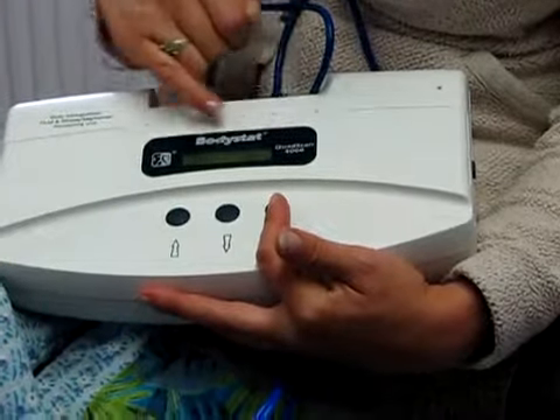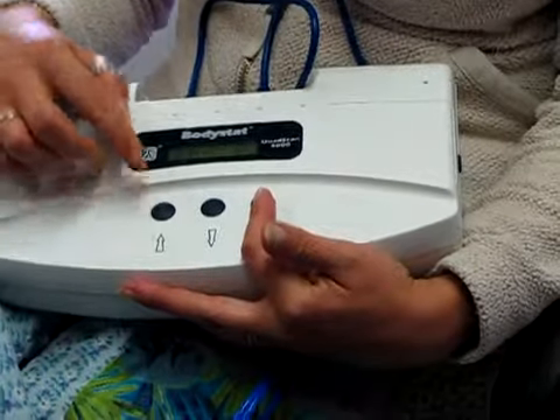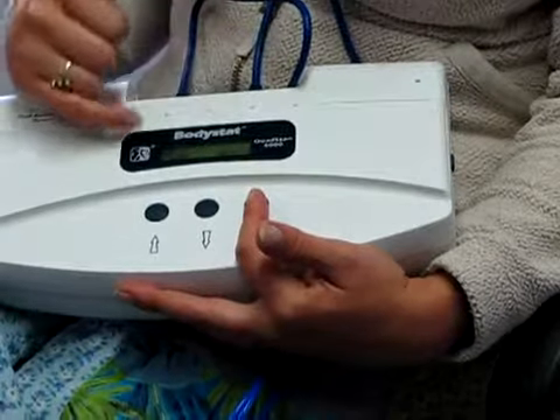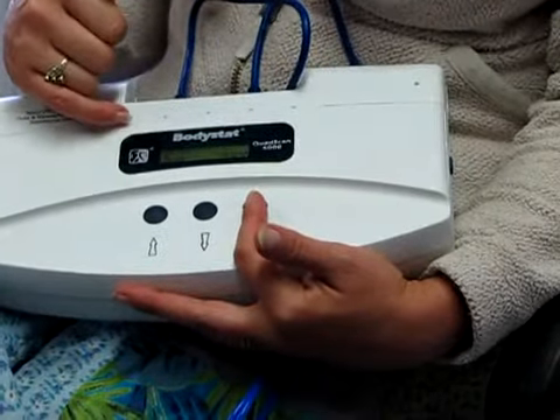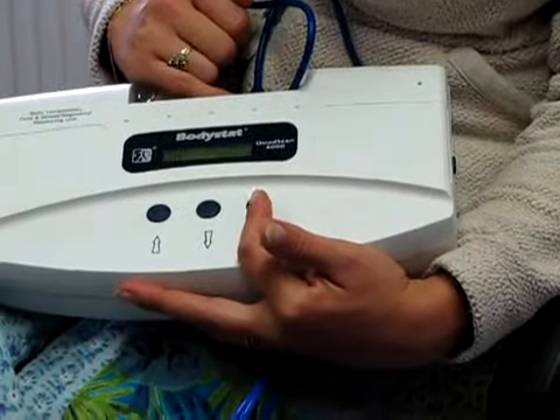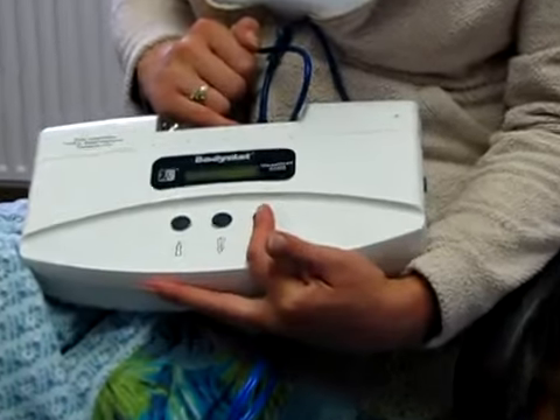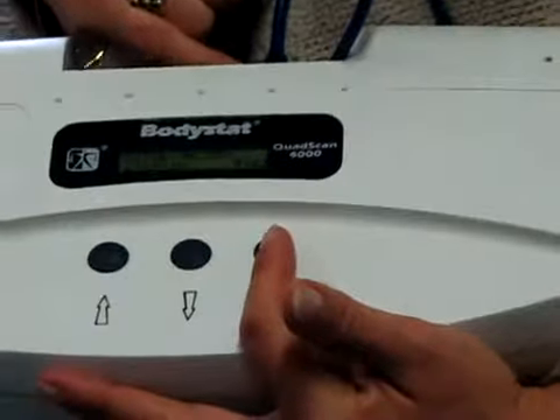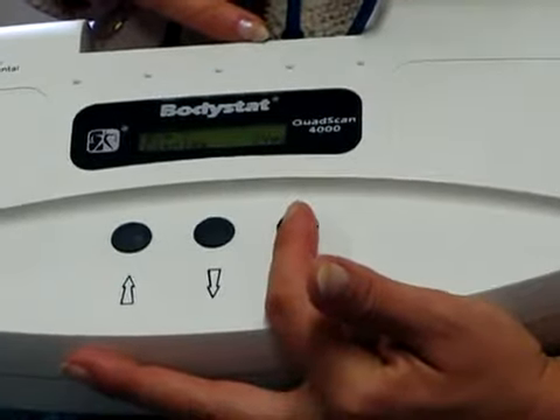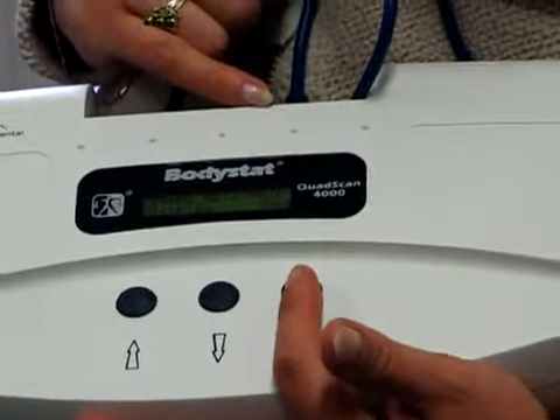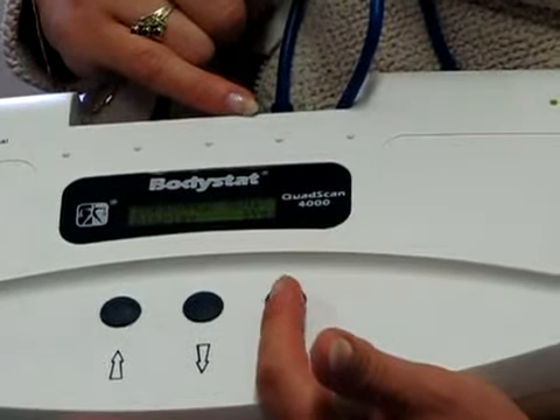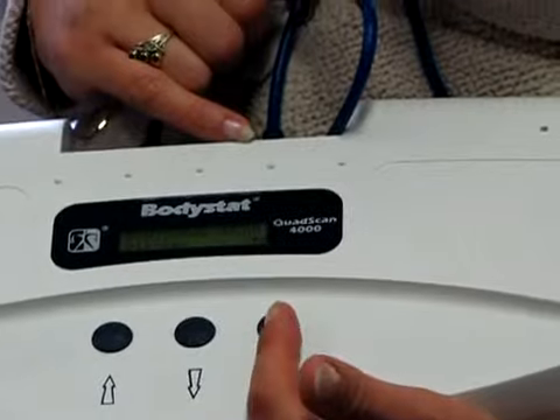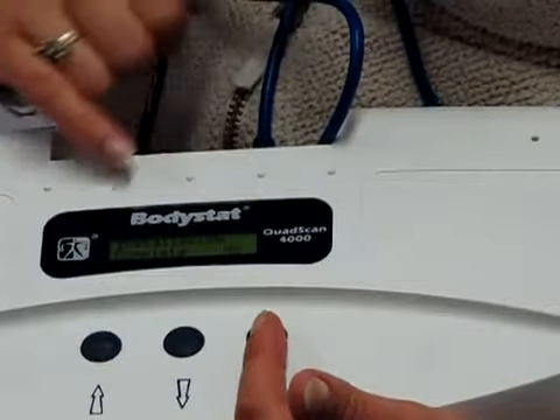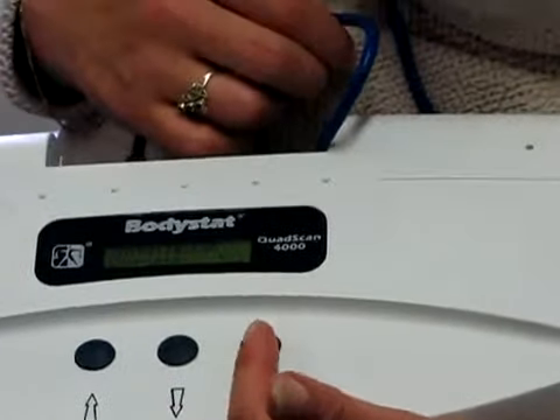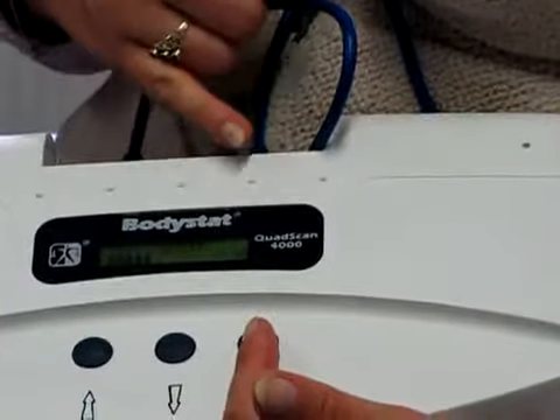Now we're just going through various selections that you can have on there. When you get to the weight and hip measurement, with some of the different parameters you can press omit, which means you don't have to input that data at the beginning. Once we get through to the end, it will ask us if installation is complete. You change the default to yes and press enter, and then those parameters that we've altered are stored within the device for the next time you switch it on and do a test.